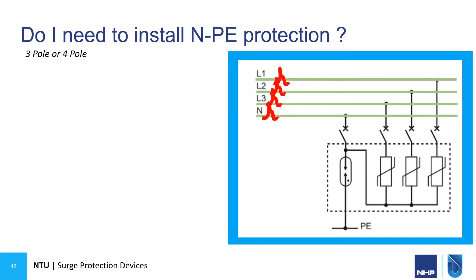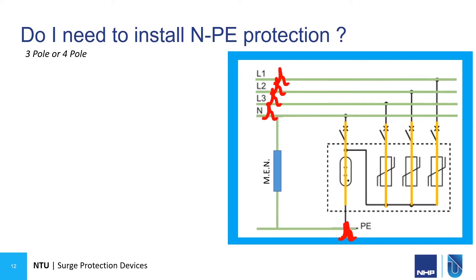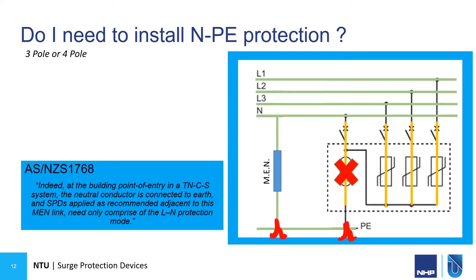Before moving on to the selection guide, I wanted to answer the question as to whether we always need to install a neutral-earth pole on our SPDs. Under surge conditions, our SPDs modify their impedance almost to zero, providing a path for that surge energy down to earth. However, if we're close to an MEN link, we already have a path from the neutral to the earth, and hence under surge conditions that fourth pole is redundant. That's also backed up by AS/NZS 1768. So in that case, we only need to install a three-pole device.